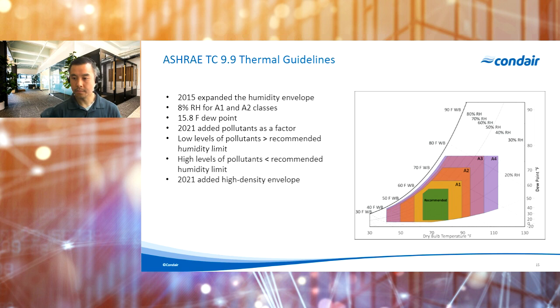Before we get into how economization is accomplished, it's good to do a quick review of thermal guidelines for IT equipment. Arguably the most important document for the design and operation of IT equipment in data centers is ASHRAE's Technical Committee 9.9's Thermal Guidelines for Data Processing Environments. The document has been around for over 20 years and has gone through several revisions since the original release. The original release had a pretty limited recommended range, about 68 to 77 degrees Fahrenheit dry bulb, and 40 to 55% relative humidity. Though, as you can see from the chart to the right, it's really greatly expanded in the last 2 decades.